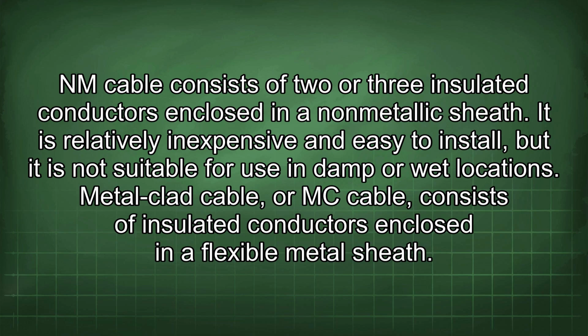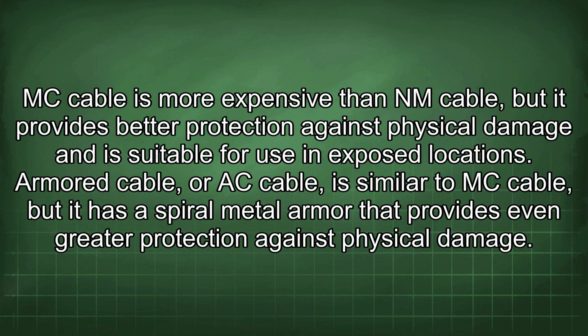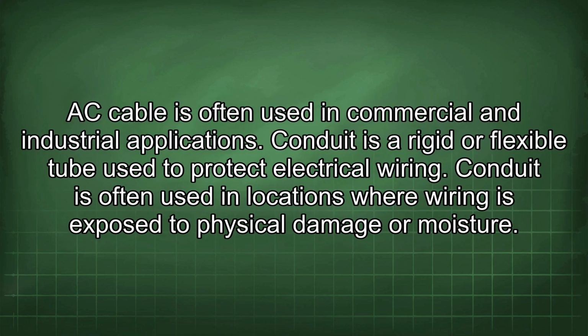Metal-clad cable, or MC cable, consists of insulated conductors enclosed in a flexible metal sheath. MC cable is more expensive than NM cable, but it provides better protection against physical damage and is suitable for use in exposed locations. Armored cable, or AC cable, is similar to MC cable, but it has a spiral metal armor that provides even greater protection against physical damage. AC cable is often used in commercial and industrial applications.